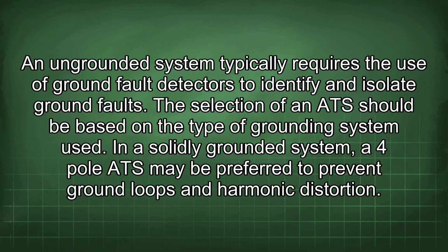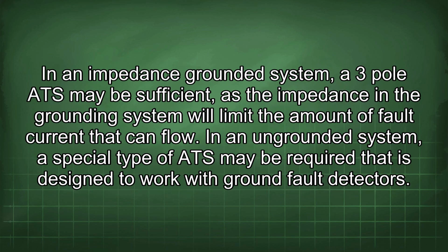The selection of an ATS should be based on the type of grounding system used. In a solidly grounded system, a 4-pole ATS may be preferred to prevent ground loops and harmonic distortion. In an impedance-grounded system, a 3-pole ATS may be sufficient, as the impedance in the grounding system will limit the amount of fault current that can flow.